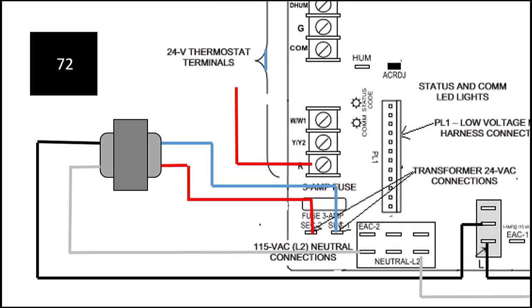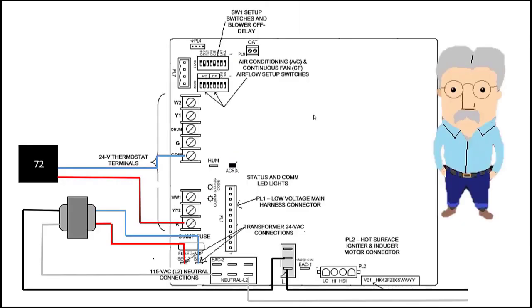Now we're going to need a thermostat. So let's wire that in. We're going to wire in our R terminal and our C terminal. And those provide power for the clock and calendar functions and programming functions within the thermostat.